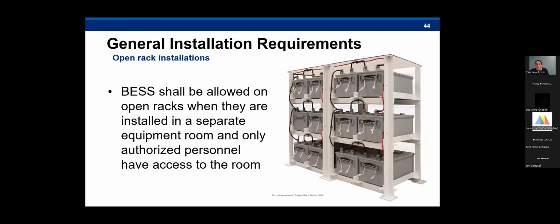So here we have the open rack installation requirement. Where systems are installed in a separate equipment room and only authorized personnel have access to that room, they shall be permitted to be installed on an open rack. This is a common theme: these systems must be secure from unauthorized access, as they can pose hazards. You really want to make sure that only authorized personnel have access to the room. And I think the open rack requirement here is much more common for lead acid batteries than it is for lithium ion. So usually you'll only see this when it comes to lead acid batteries.